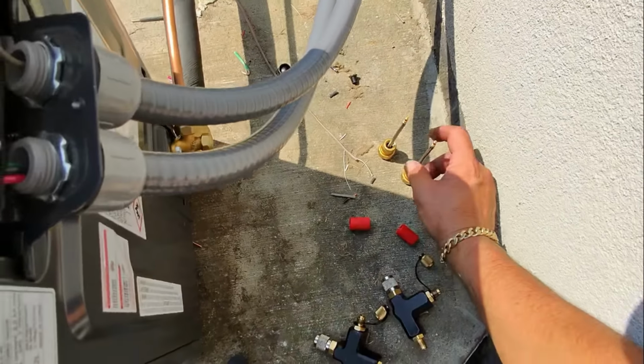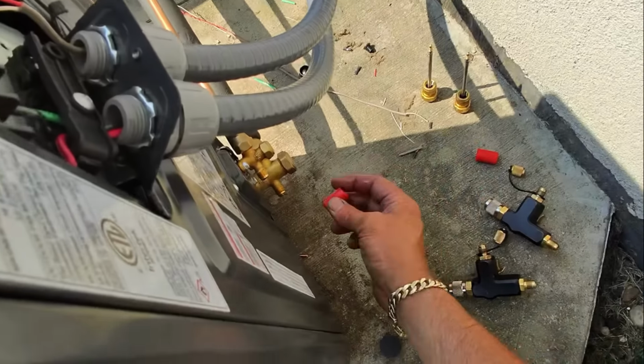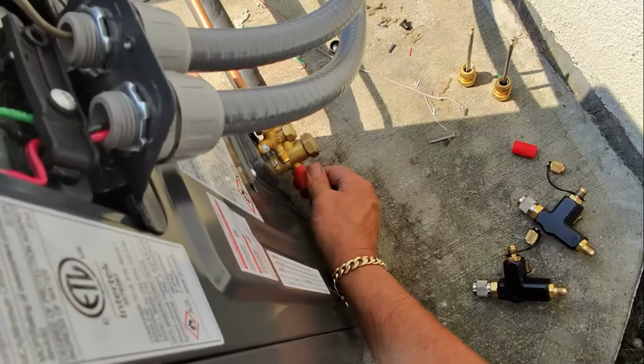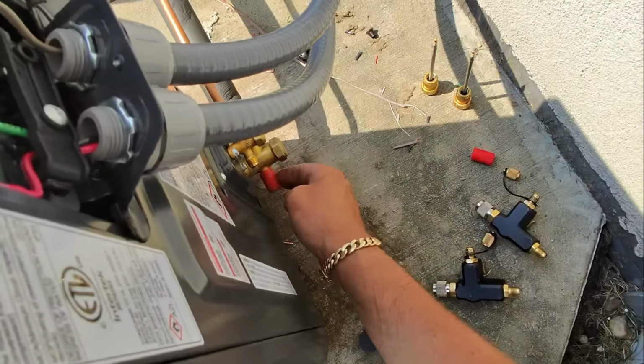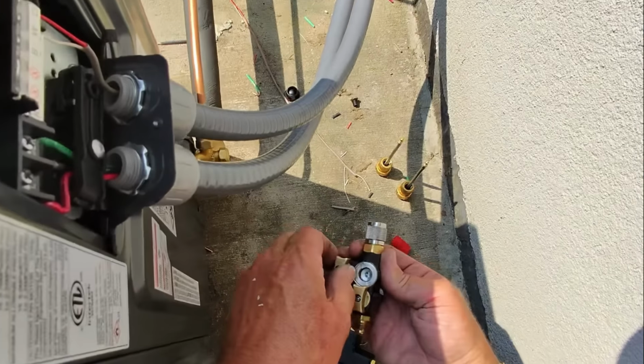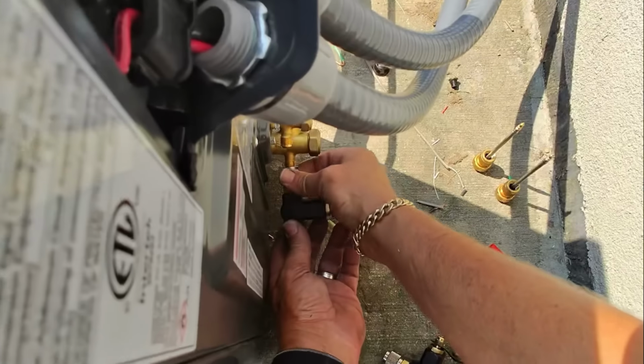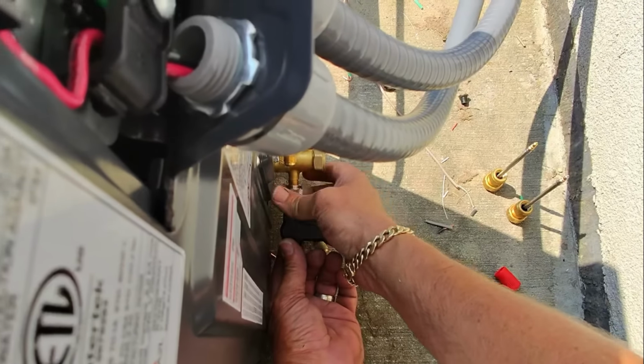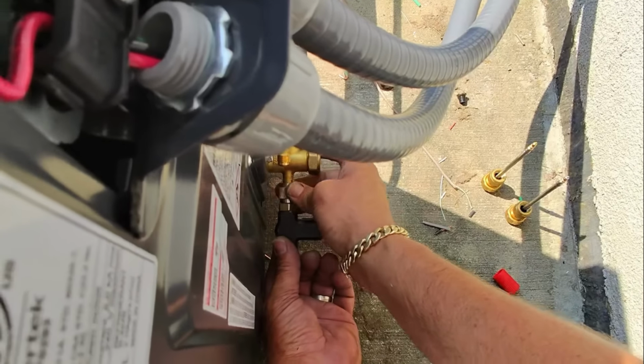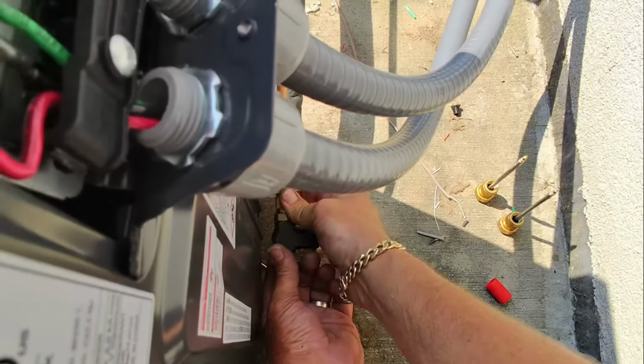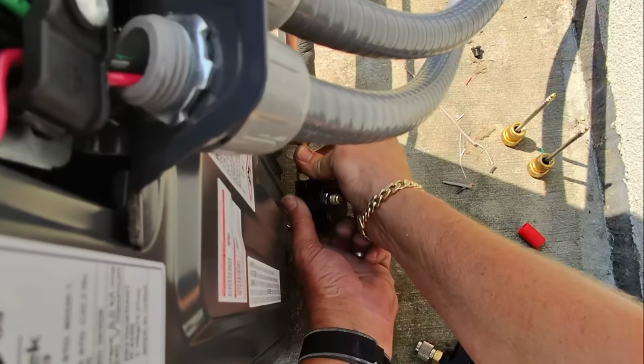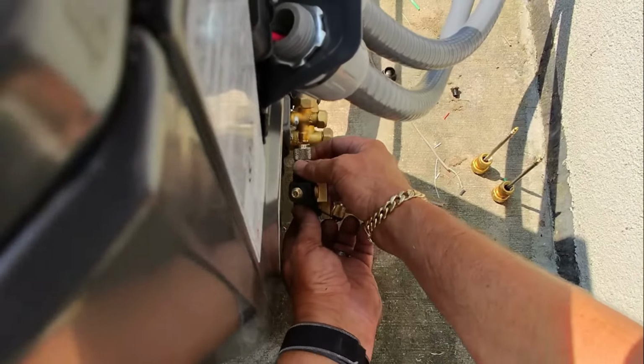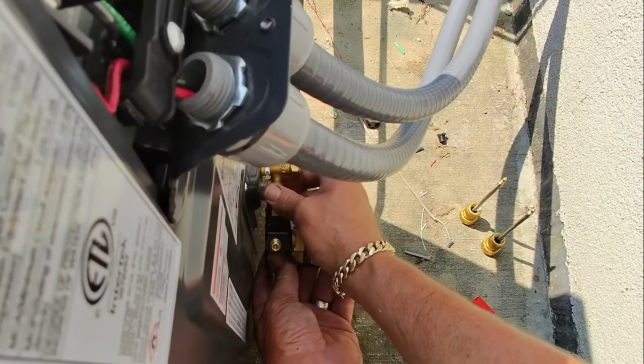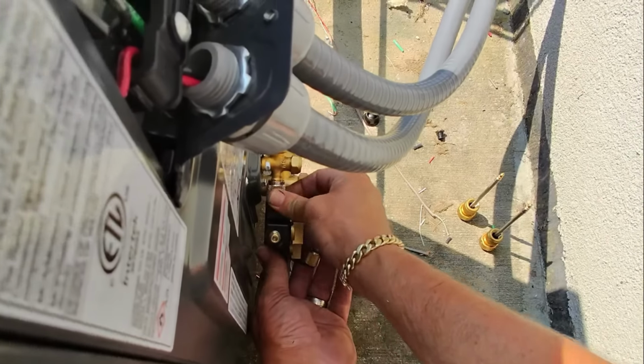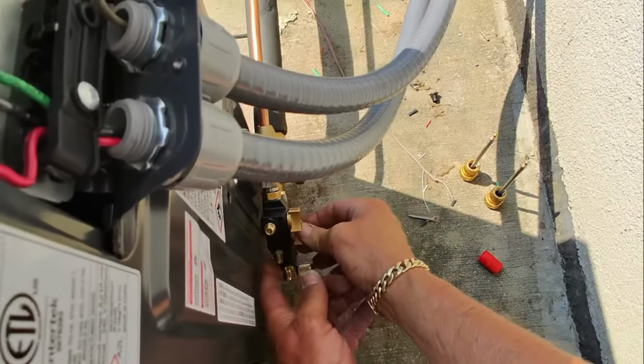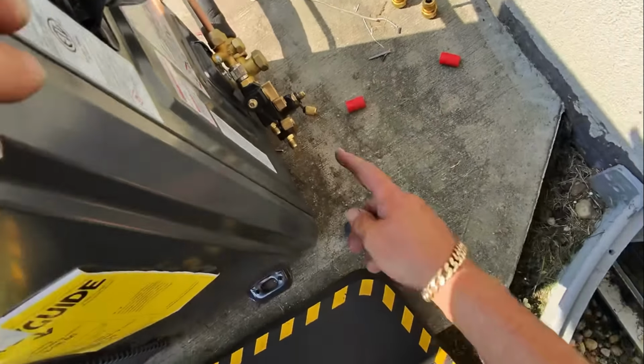Okay, those are the 2 core valves. I'm just going to keep that back on there. Actually, hold on, let me do this right now. Let me put the schrader core removal tool on both. You want to keep the line set not open to the atmosphere at all. I know that's impossible to do, but if you limit the time the line set is open to the atmosphere, you'll have less chance of non-condensables getting in there.